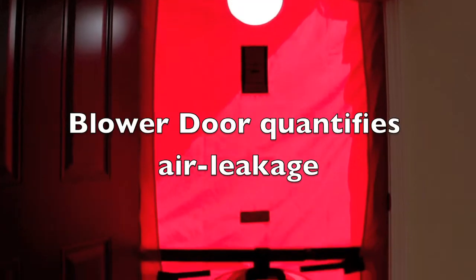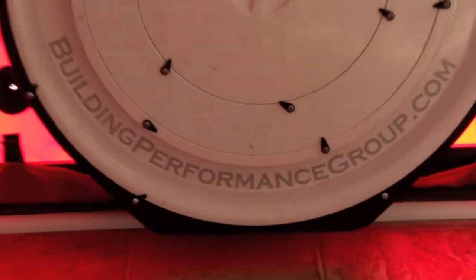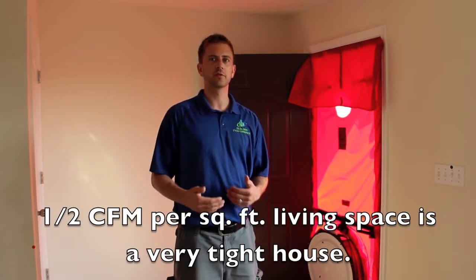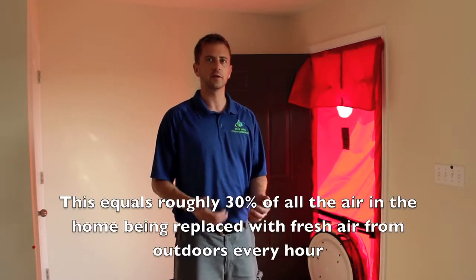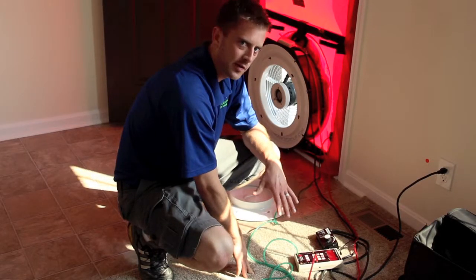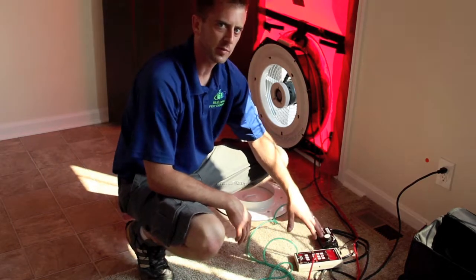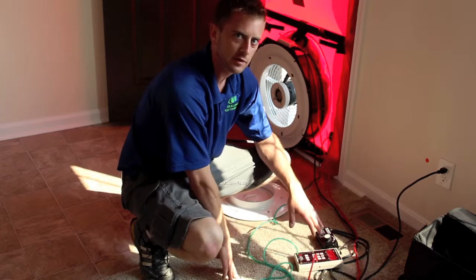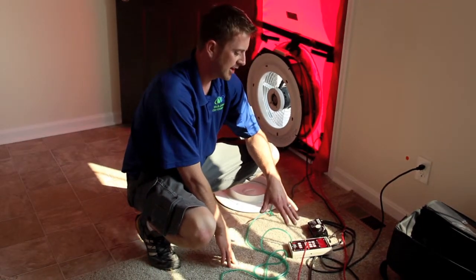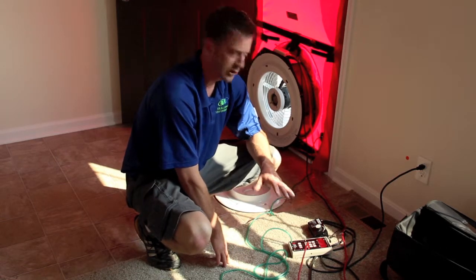Now we're inside and we've got the blower door set up. I'm going to do an air leakage test on the house. This house is about 2,055 square feet on a full crawl space, so I'm hoping to see a number close to about 1/2 CFM per square foot of living space — something around 1,100 to 1,300 CFM. Now I've got the house depressurized at 50 pascals, and the pressure gauge is showing that at that pressure difference, this house is leaking about 1,190 CFM, which is really good for a 2,100 square foot house. A good start to the process.